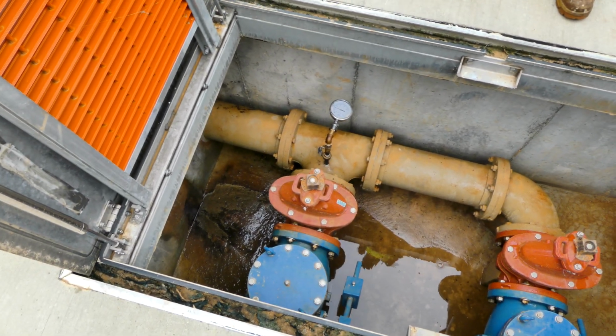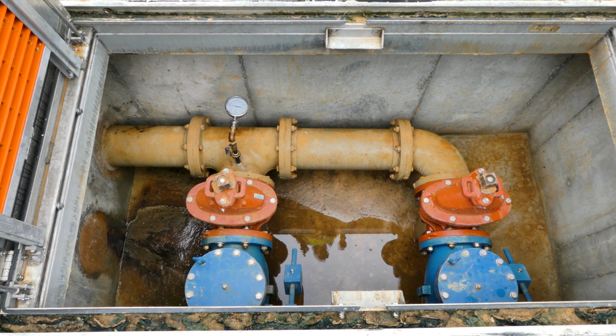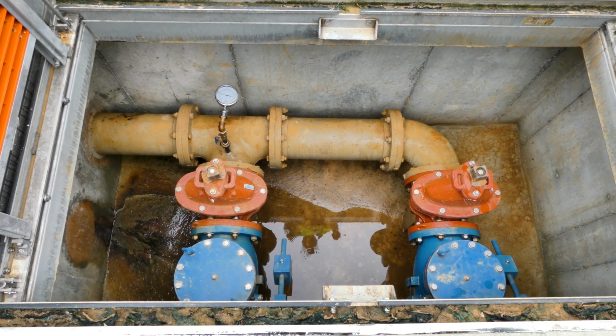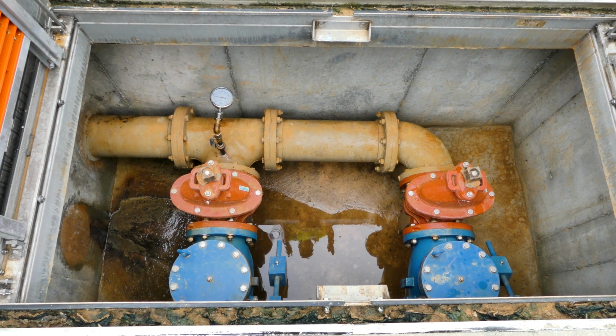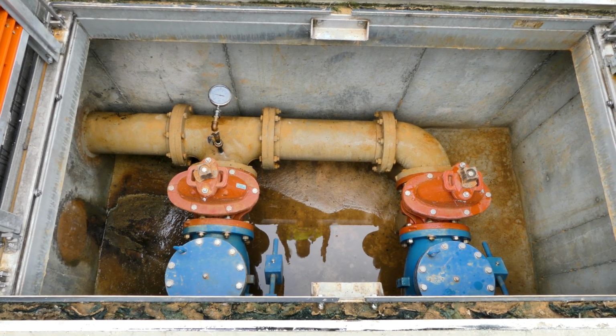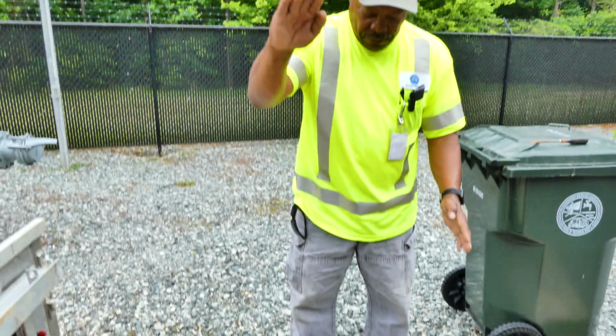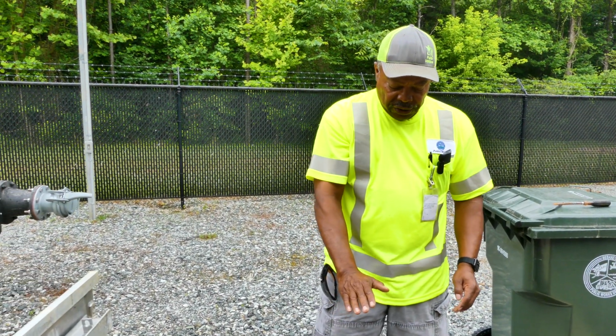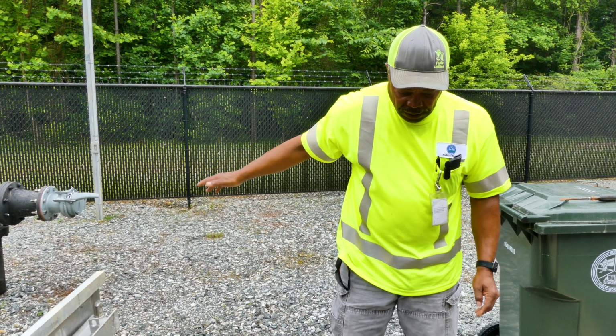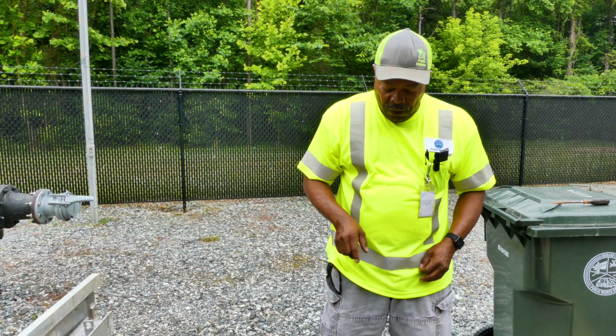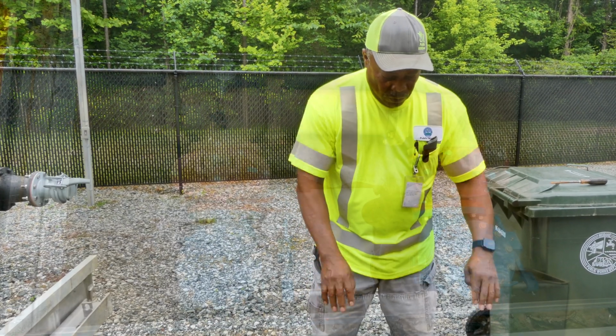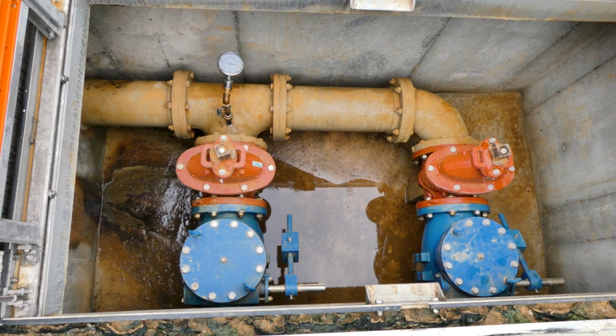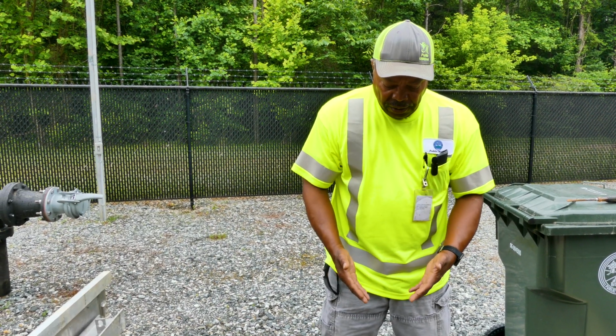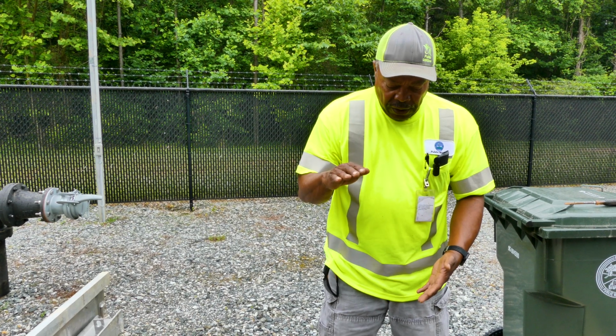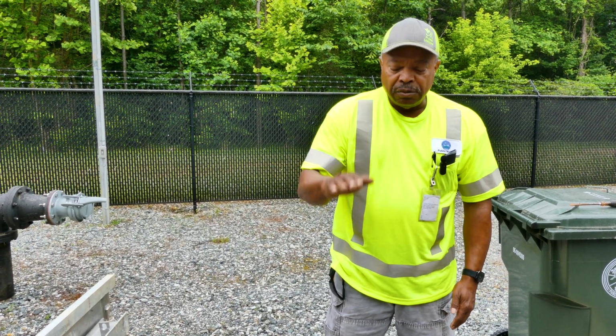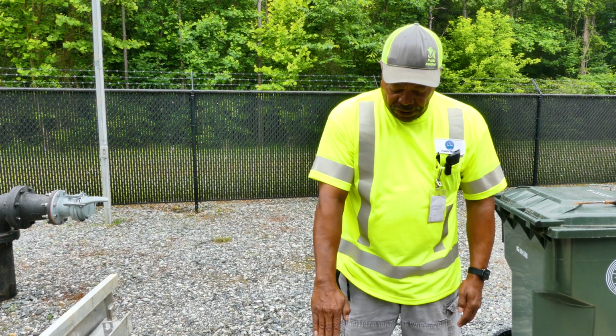Like I said before, this is the dry well. We have 2 gate valves and 2 swing arm check valves. When the pump is operating, the check valve arm rises up and lets the wastewater continue to flow out of the system. Once it's operating, we just take a visual look to make sure the arm is raising up, and when the pump shuts down, the arm falls back down into the right position.